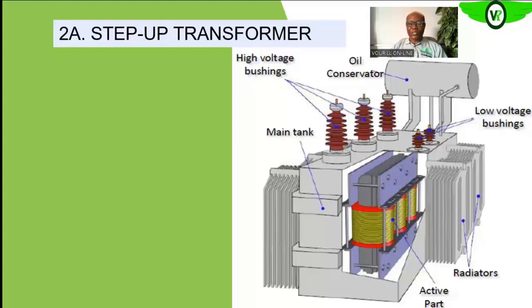In the course of operations, because of the effect of I squared R, power losses are bound to occur around the windings of the transformer. These power losses definitely come in the form of heat, and we need to take that heat out of the transformer. That is where the transformer oil comes in. Apart from cooling the windings, the transformer oil also helps in insulating the active parts from the inactive parts of the transformer. Let us see each of these component parts of the transformer in a little detail.